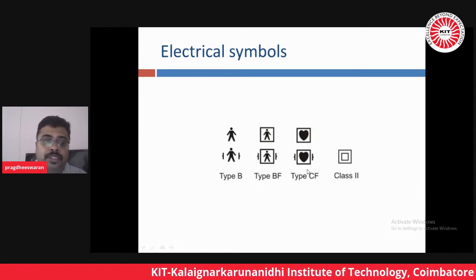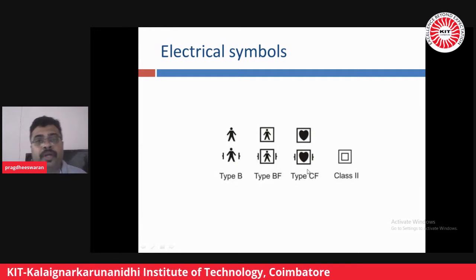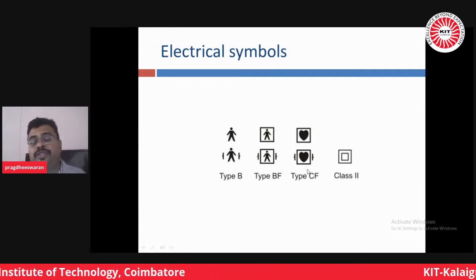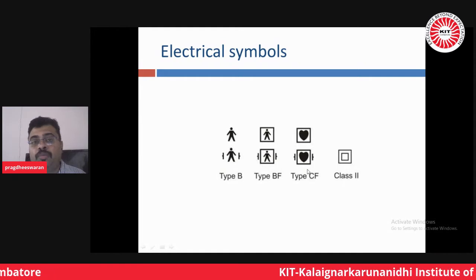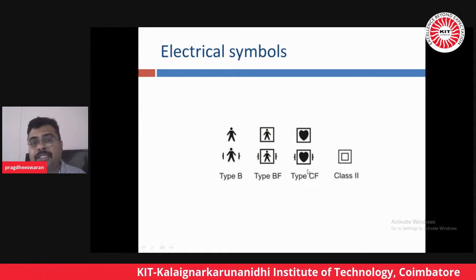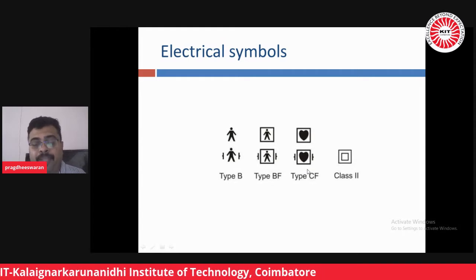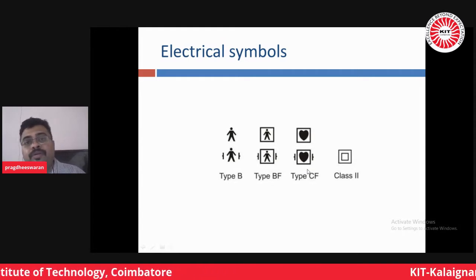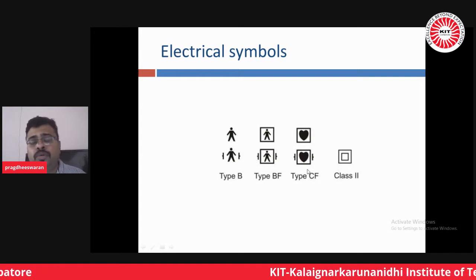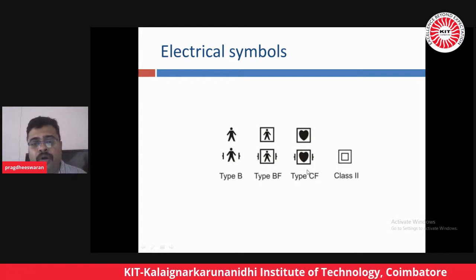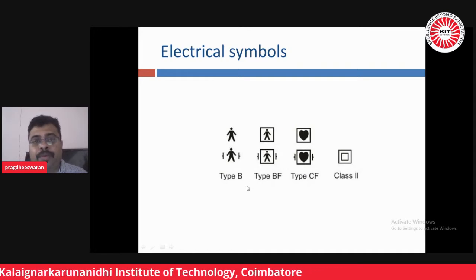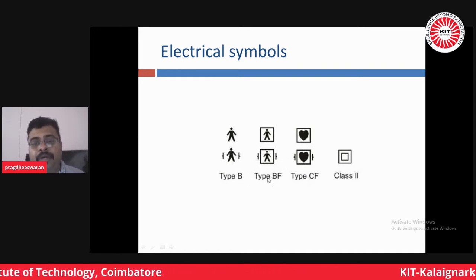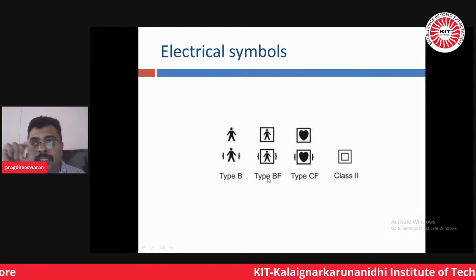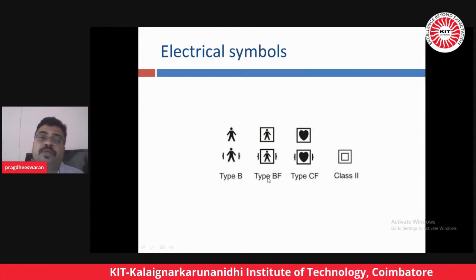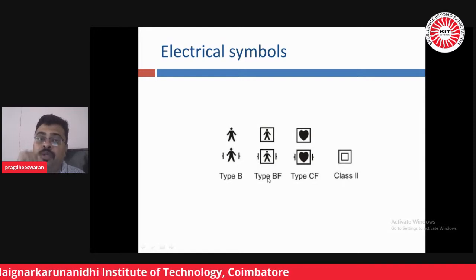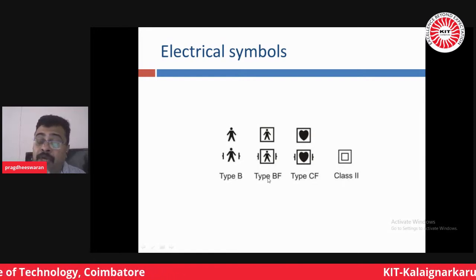In hospitals, frequent equipment failures used to happen, right? Because of electrical socket issues, the single faults increase the leakage current and cause faults on capacitors, and eventually the equipment will fail. So with the single fault, whether your medical equipment, as per the classification of type BF or type CF, is passing the leakage current value, that is what you are going to test with the performance test and safety testers.